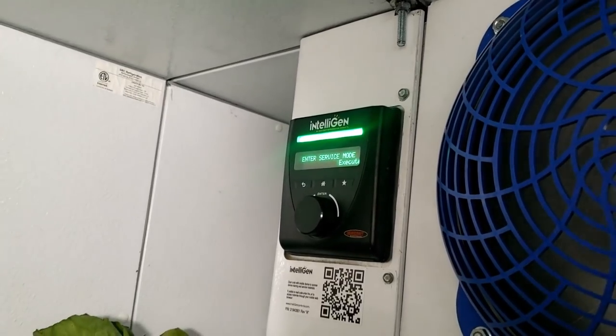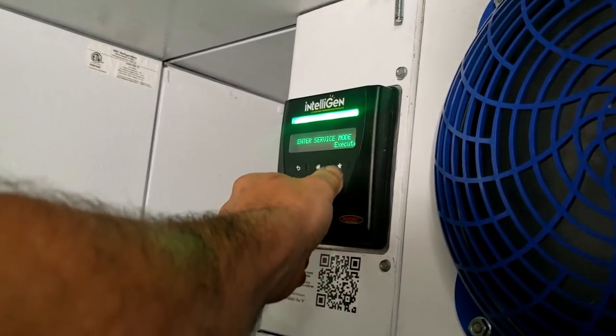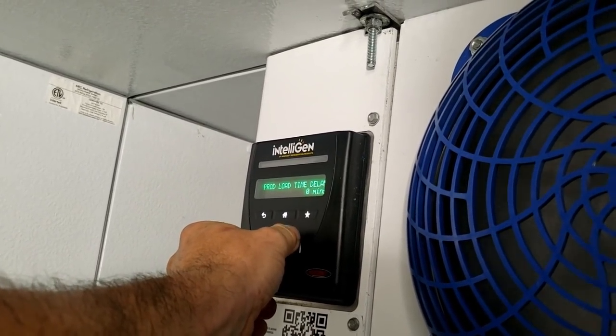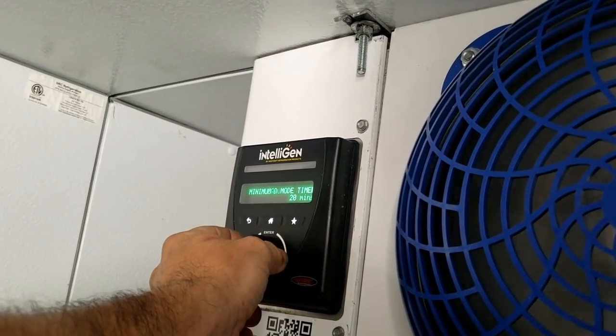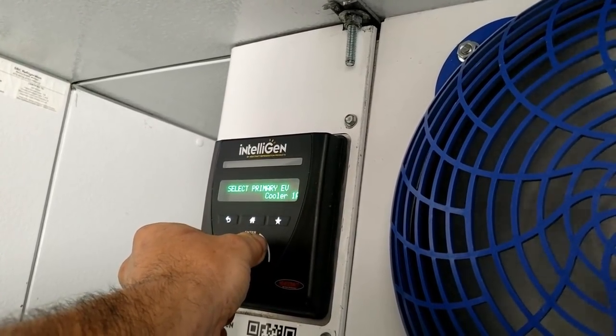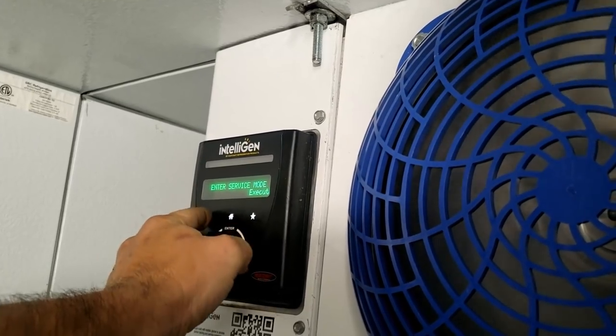All right, so I had to get out of the service mode. So box temp set point differential's 2 degrees. Preload time 0 minutes. Minimum on, minimum off. So everything's good to go. Yeah, we're just going to have to get out of here and call it a day. Unfortunately. So they're just going to have to deal with it until we get the new...